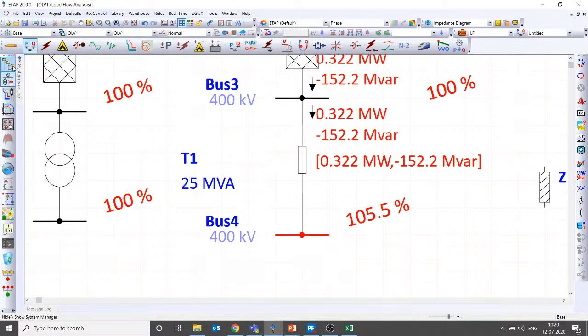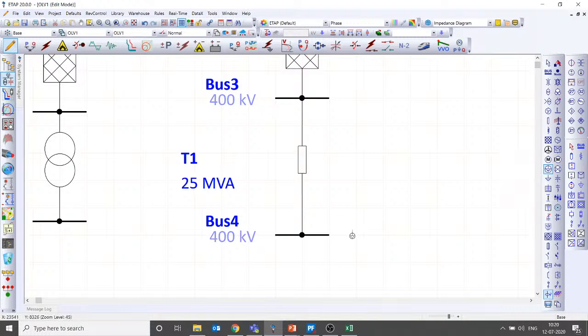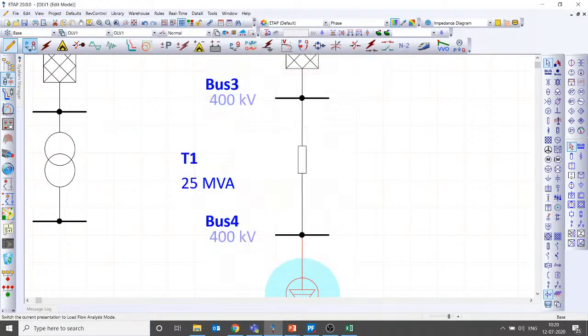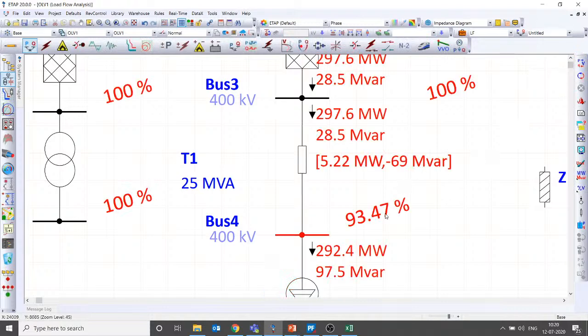If you put a load of, for example, 300 megawatt, even at say 0.95 power factor, say like 300 megawatt with say 100 Mvar, about 95 power factor. If we are running a load flow for this case, you can see the receiving end voltage falls down to 93.47, which is not acceptable. What I mean by that is, during loading conditions, the voltage goes to under voltage, and during the no load conditions, the voltage goes to over voltage. In both the cases, the receiving end voltage is not acceptable.